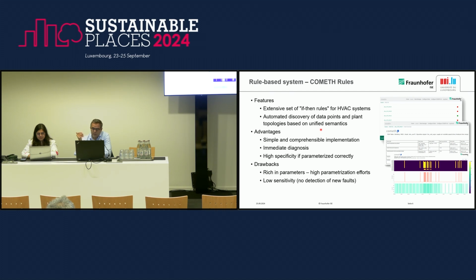The advantage is that it's very simple, the implementation is quite straightforward, it enables an immediate diagnosis, and it is highly specific if parameterized correctly - meaning you don't get false positive messages. The drawback is that it's a bit difficult to transfer from one building to another, it's very rich in parameters that you have to set, and it cannot detect faults that are not programmed.